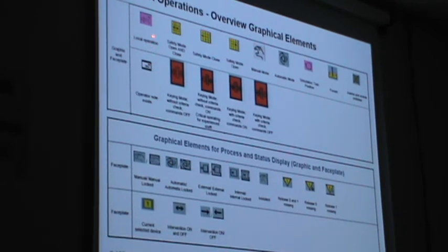And again, this is for the local operation indication. If something is put in local, some switch gear, you operate the pump or motor from the switch gear, you will get this kind of information, local operation. All the switch gears and pumps have the provision to operate from local also. But the operator should give the command to the field: you can operate in local, so I will give you the permission. That permission the operator can give.